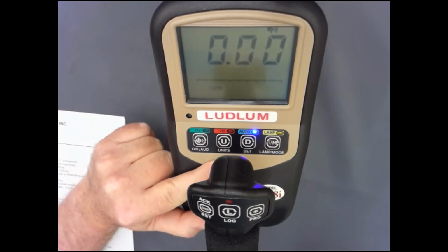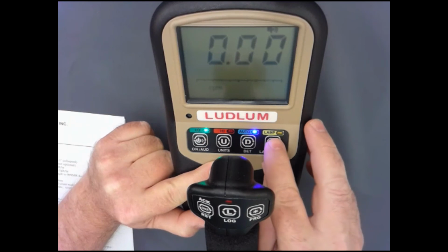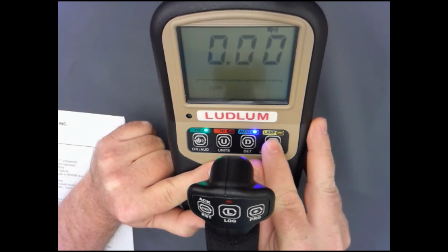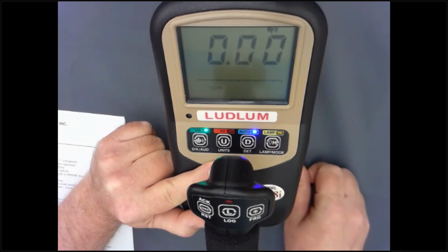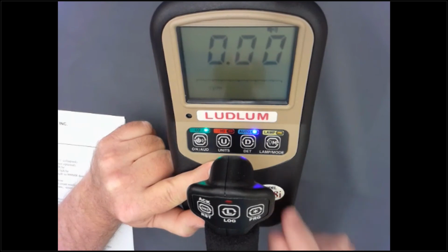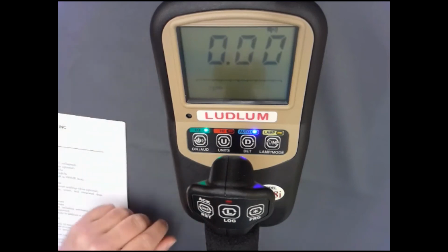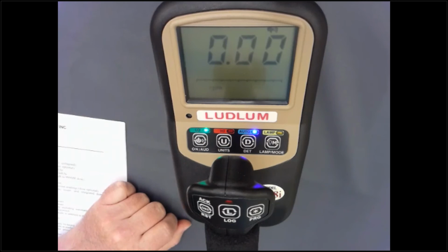Another feature of this is the mode button, and the mode button is used to switch through the available modes. As Ryan mentioned, we do have a rate mode, a max mode, a scaler count mode, and an integrate mode. The instruments are shipped default with the external detector configured for the rate mode, the max mode, and the scaler count mode, and without the integrate mode enabled. But it can be enabled using your software or going through a setup menu. Internally, the default for the internal detector is the rate mode, the scaler mode, and the integrate mode. And again, if you wish to have a max mode on the internal detector, you can go through the setup menu or make an adjustment with the software.